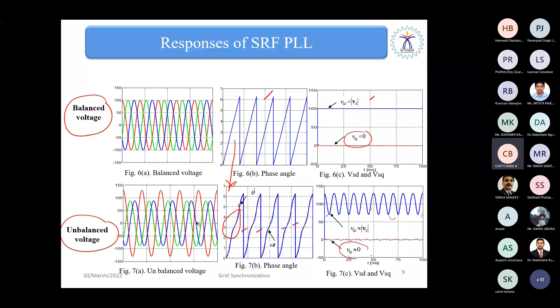In the meanwhile, the Q axis component is not at all 0. So that is why the phase lock loop cannot be used for estimating the phase when the grid voltages are unbalanced. So across the globe, a number of researchers have made an attempt to detect the value of the phase angle very accurately during abnormal grid voltage conditions. Over 150 algorithms have been proposed in the recent literature, including IEEE Transactions.